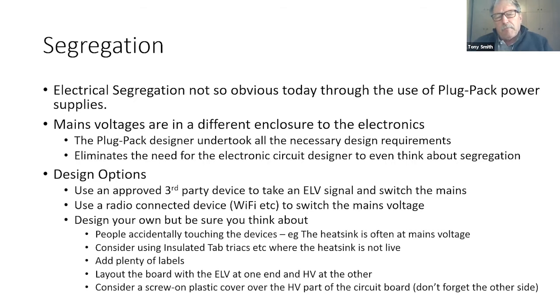However, if you've got mains voltage on a PCB, you've actually got to think about this again. So there's other aspects - you could design it yourself, or use a third-party device where you put an extra low voltage signal on one side and it switches the mains for you, as an approved device. You could use something like a radio switch - a third-party plug pack that goes in a power outlet, you plug your device into that, and you signal by Wi-Fi, so you've physically got no wiring between mains and ELV.